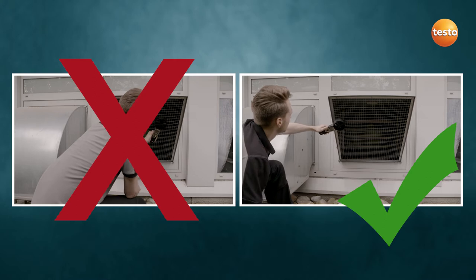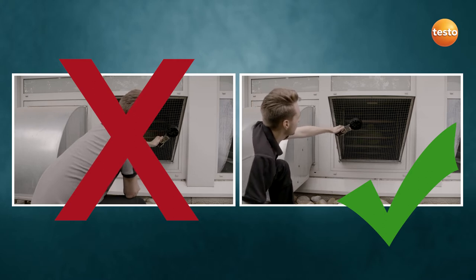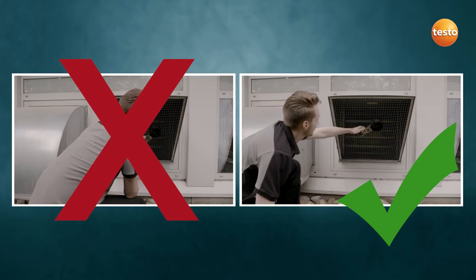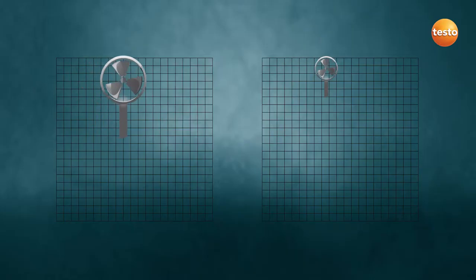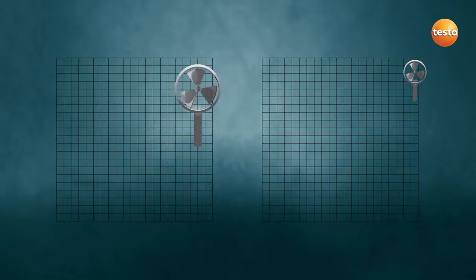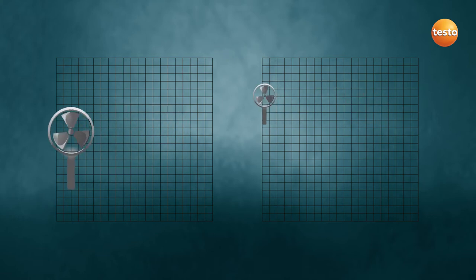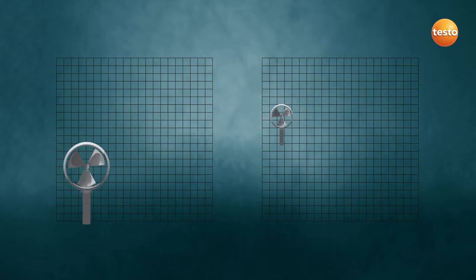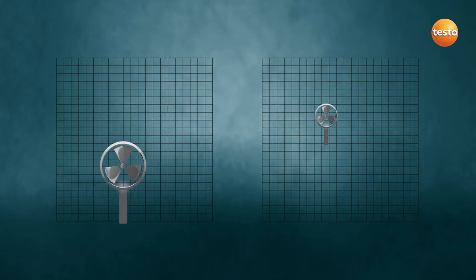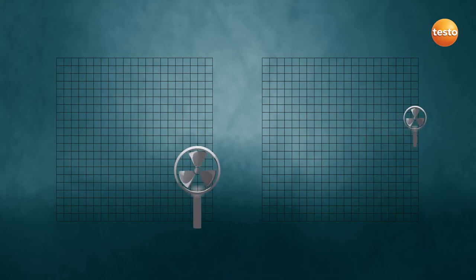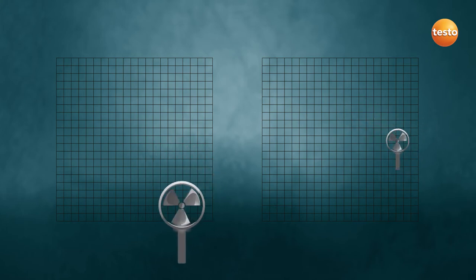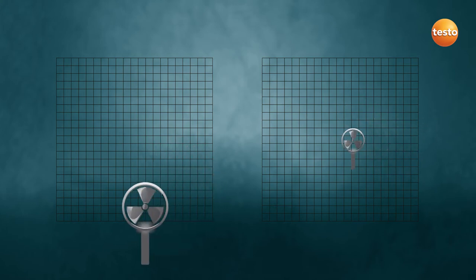The best method is to move the vane across the grill surface at a distance of 5 cm. Vanes with 100 mm diameter are better suited to measuring than instruments with smaller vanes, as the flow values are integrated and averaged over a larger area. Integrating the same area with a smaller vane takes significantly longer.